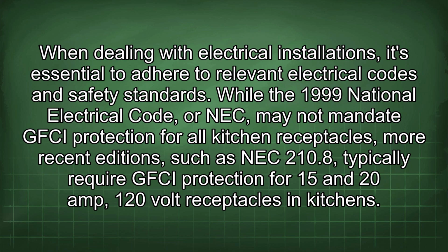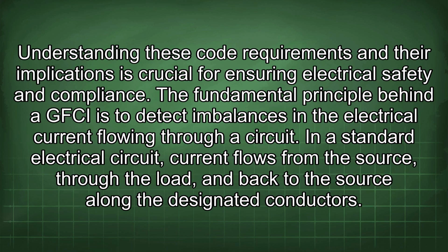When dealing with electrical installations, it's essential to adhere to relevant electrical codes and safety standards. While the 1999 National Electrical Code, (NEC), may not mandate GFCI protection for all kitchen receptacles, more recent editions, such as NEC 210.8, typically require GFCI protection for 15 and 20 amp, 120 volt receptacles in kitchens. Understanding these code requirements and their implications is crucial for ensuring electrical safety and compliance.